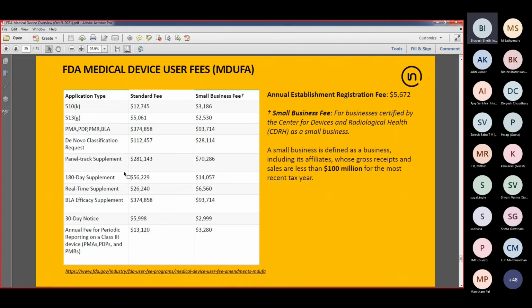So a lot of companies, definitely all the startups, would be eligible to apply for a small business. But it's again a formal process where you have to share your financial documents, your tax returns, to demonstrate to FDA that you're indeed a small business. And you get a small business designation number in return, which you need to indicate on your regulatory submission filing in order to get the benefit of the reduced fee. So that's the fee structure, as you can see. I mentioned 510K submission is popular and most sought after mode of application. That's because De Novo is a more time consuming and stringent submission.